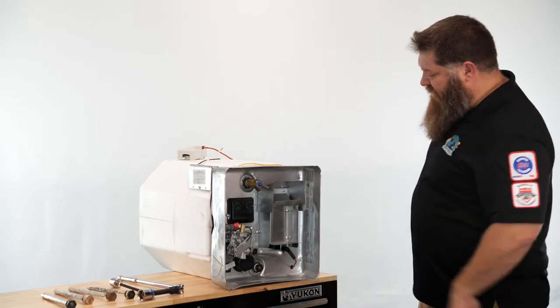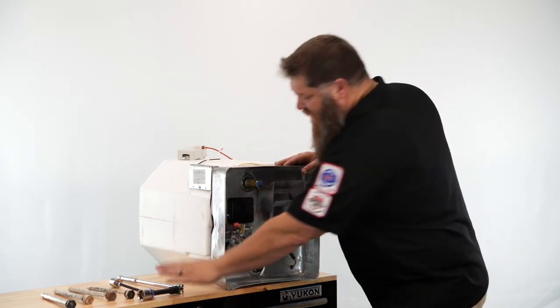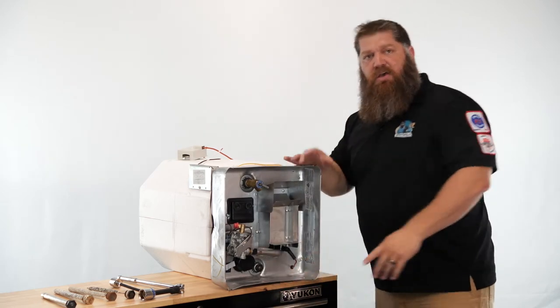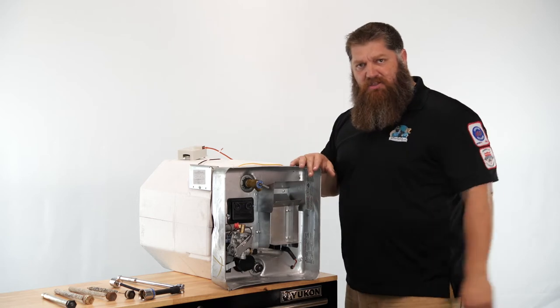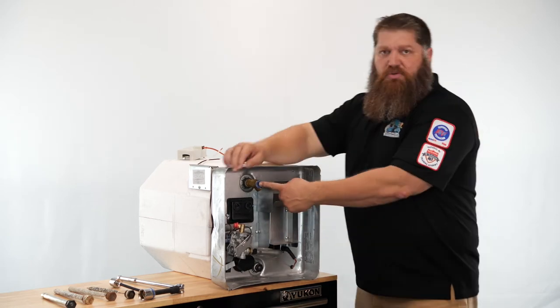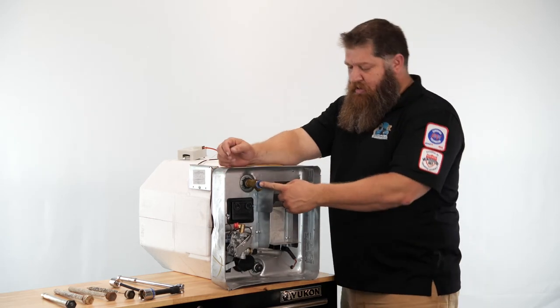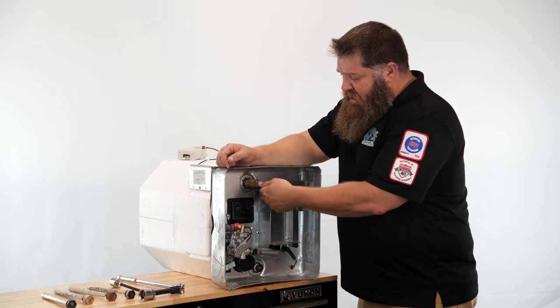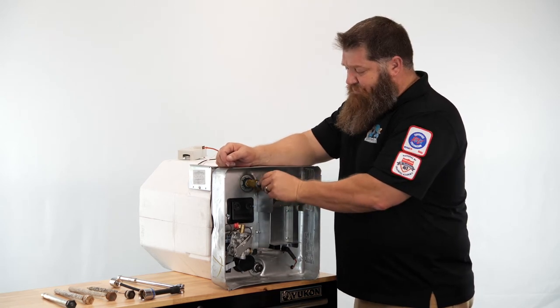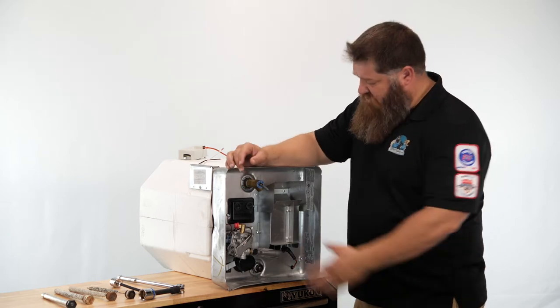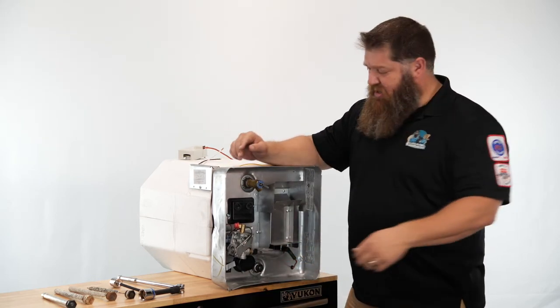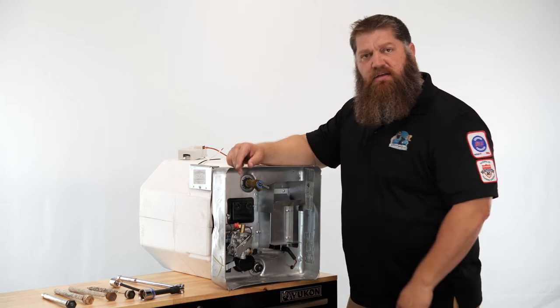Now we've got cold water inside in here and we're not grabbing our wrench to go ahead and pull this off. We've got to depressurize this. Because there was heat in here we actually have about 150 pounds of pressure. We want to reach right over here to our pressure and temperature valve and we want to carefully just open this up briefly and allow a depressurization. We'll have water come down there that's totally fine. But we'll depressurize the tank.